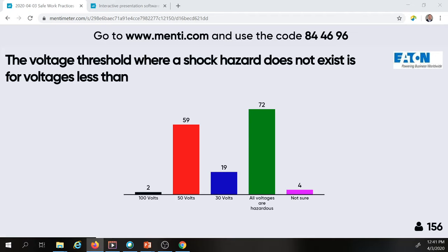So here's where you're at. If you have your 70E document, you're in 130.4, and I just had my thumb over it. If you go over to the restricted approach boundary, that's one area. When you get into the shock boundaries is where you start to discuss the voltage levels. The restricted approach boundary tells you that no qualified person shall approach or take any conductive object closer to exposed energized parts than the restricted boundary unless one of the following conditions applies: the qualified person is insulated or guarded from energized electrical conductors or circuit parts operating at 50 volts or more. So your 50 volt number is what you're looking for from a 70E perspective.